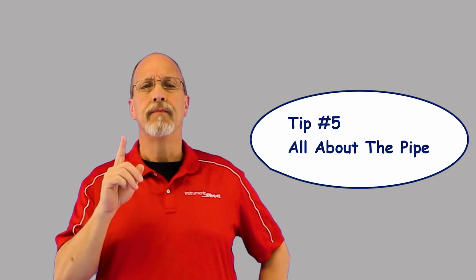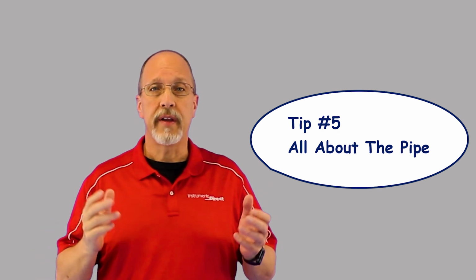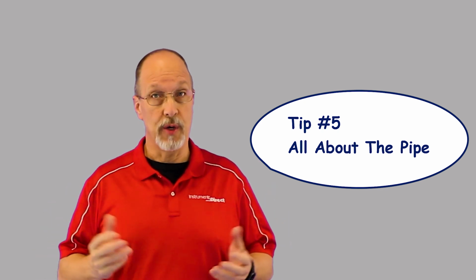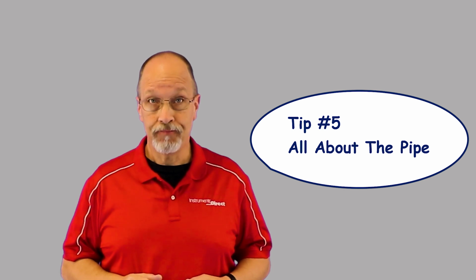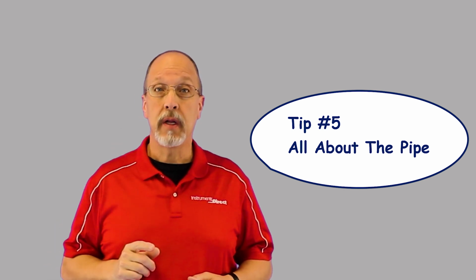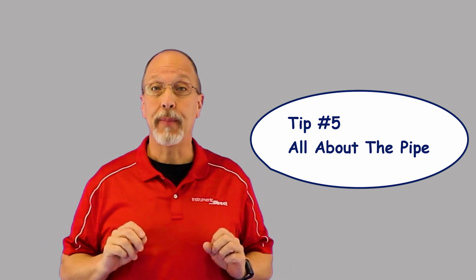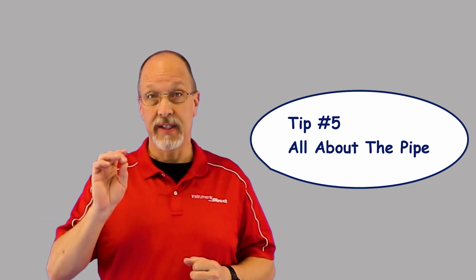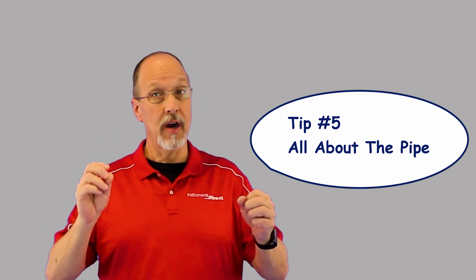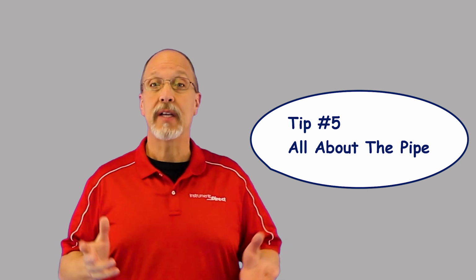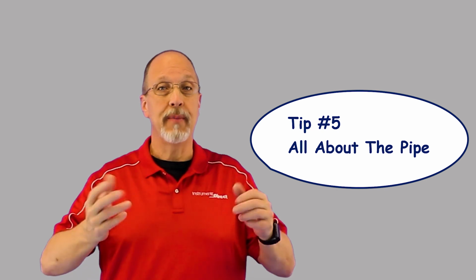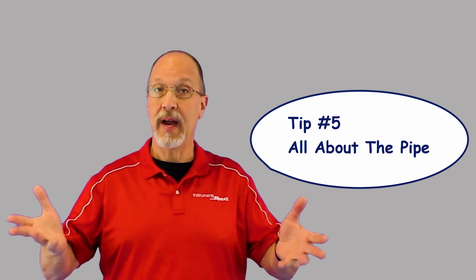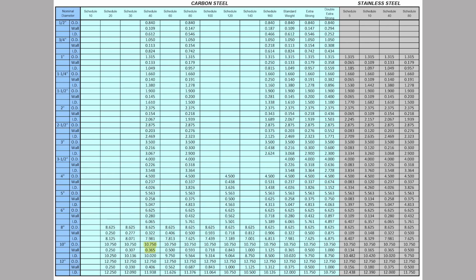All right, time to program your meter with the type of processed liquid. In most cases, that'll just be water. Then the pipe material and the correct pipe ID and wall thickness. This is a classic case of garbage in, garbage out. If you don't know the pipe size, well, just wrap a tape measure around the pipe and divide it by pi, 3.14, to get your pipe diameter. Then you can match it to an ANSI pipe chart to confirm what pipe size and material it is.